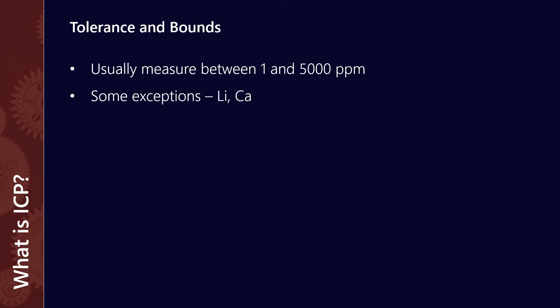The other thing that's worth noting is the tolerance and bounds. So what are we capable of measuring? Generally, for most of the different elements, we can measure between 1 and 5000 ppm. Now we don't typically see that much lithium in oil analysis samples, unless maybe there's some contamination with a lithium or a lithium complex grease. And calcium can actually be tested to a much higher threshold. So we can test from anywhere from 1 to about 20,000 ppm in that case.